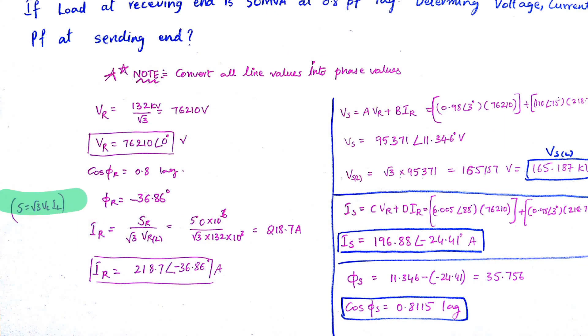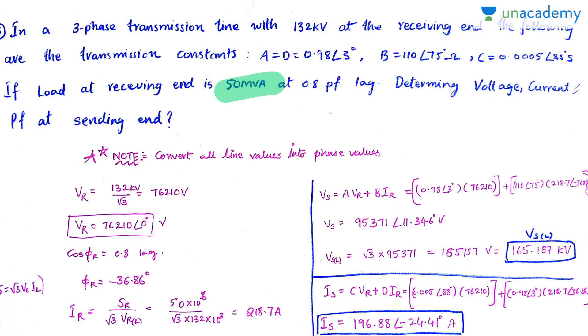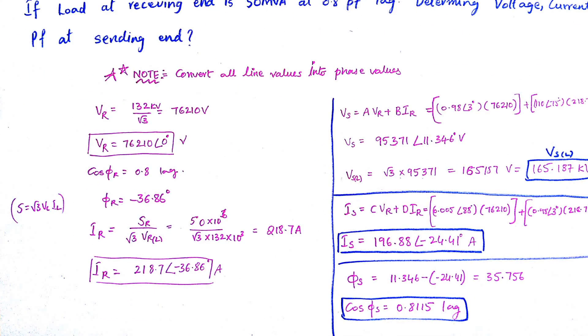I want to find the receiving end current. Receiving end current can be found by this relation: S equals root 3 times VL times IL. The receiving end apparent power is given - 50 MVA. So Ir will be Sr by (root 3 times Vr). You are just going to do with line values. The reason is Ir also you will be getting as line value. But Ir line equals Ir phase, because although not specifically mentioned, we will assume the entire system is connected in star. And you know in star, line voltage equals root 3 times phase voltage, but line current equals phase current. So there is no problem there. You proceed with this and get the current: 218.7 Amps.